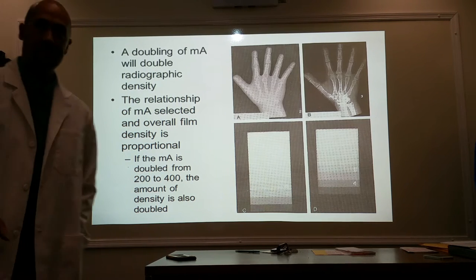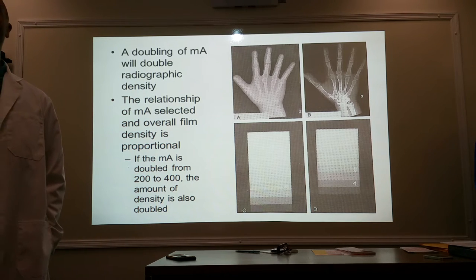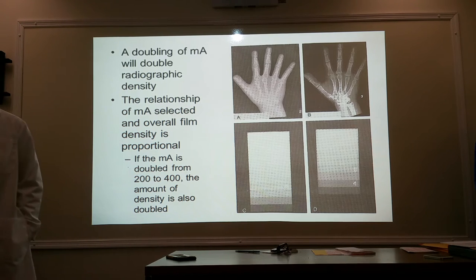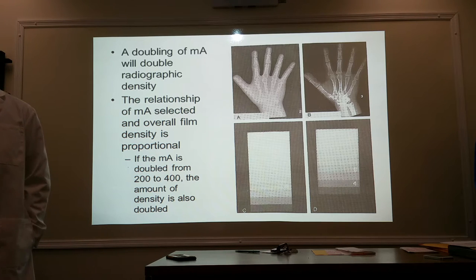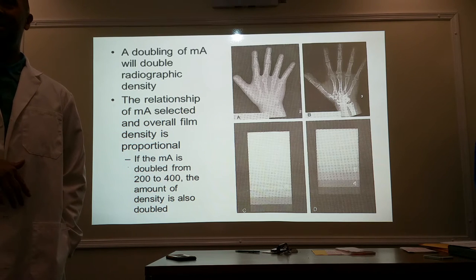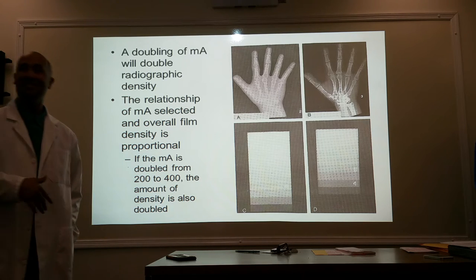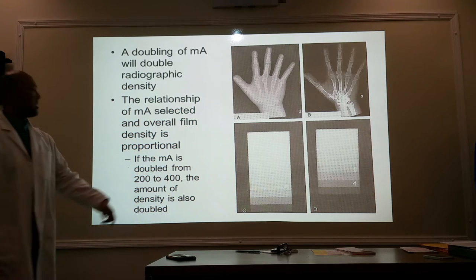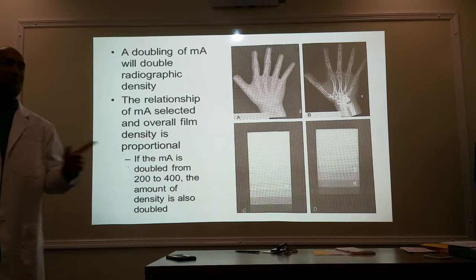Unlike KV, your adjustment in MA is proportional to the density you're trying to produce. So when you double your MA, you're also doubling your overall radiographic density. If I double my MA, it's going to be twice as dark. If I cut my MA by half, it's going to be half the density. The relationship between MAS selected and overall film density is proportional.